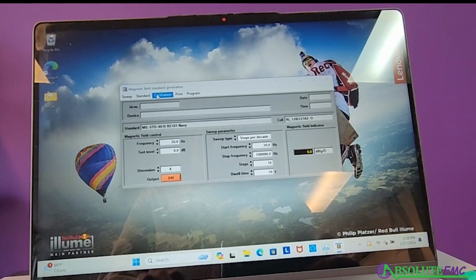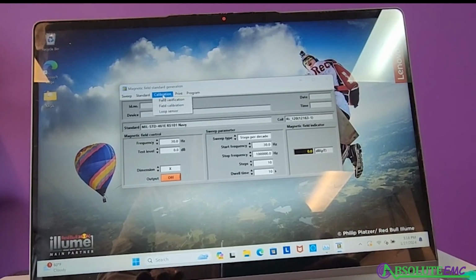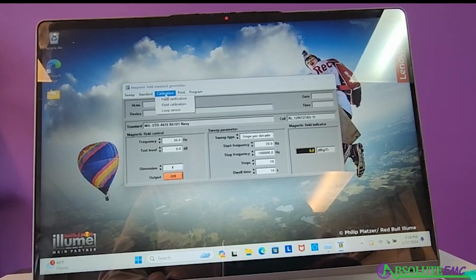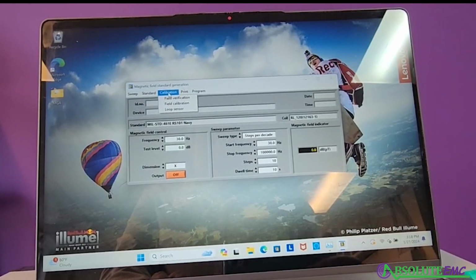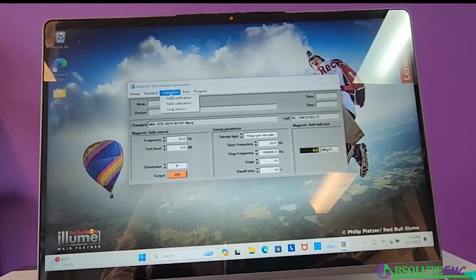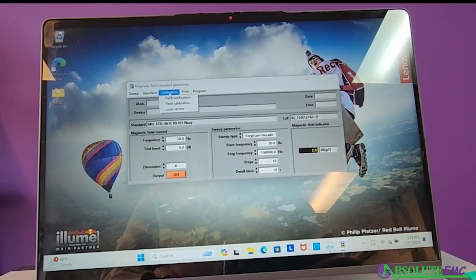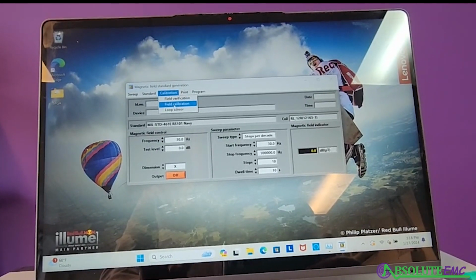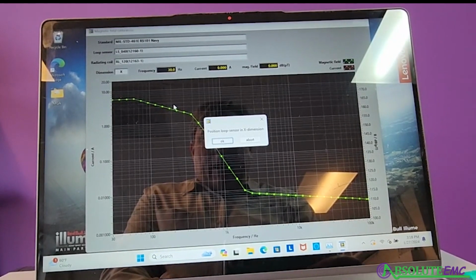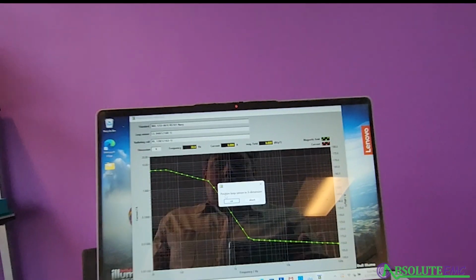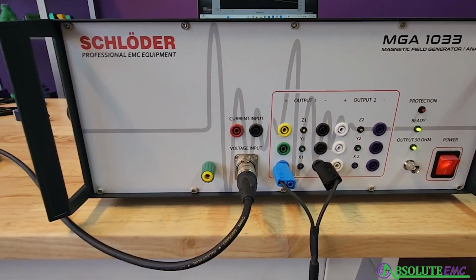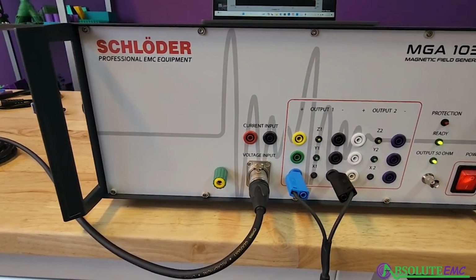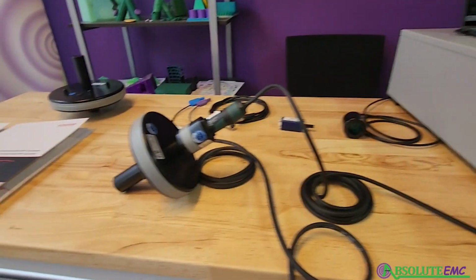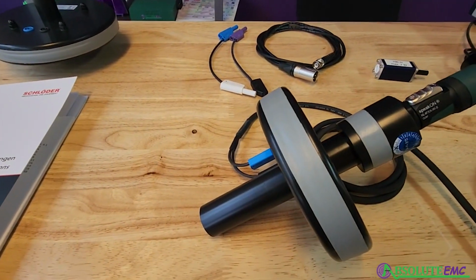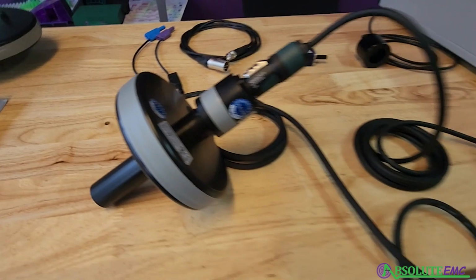what's Windows doing now. You have a choice between a field verification and a field calibration. A field verification just checks at one frequency, and a field calibration does a whole frequency scan. So to bring that up, it tells us to put the loop sensor in the X dimension, because that's what we're going to connect. That's what's set in the setup. We have our setup here with the loop and the loop sensor.